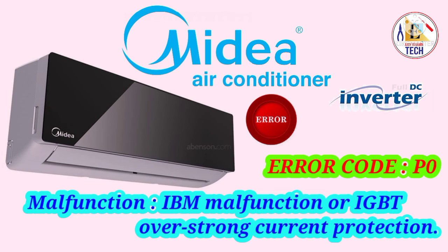When you see the error P0, it means your IPM or your IGBT is defective. In your outdoor PCB, these are the two components which are installed. If your IPM is not working properly, then it can't give proper command to your compressor and you will get the error P0.